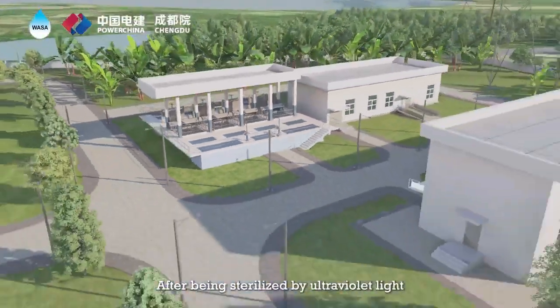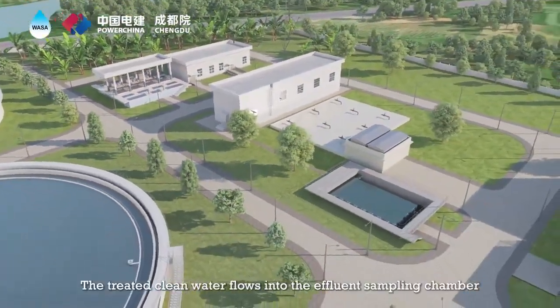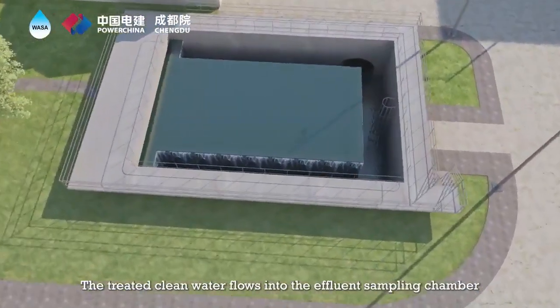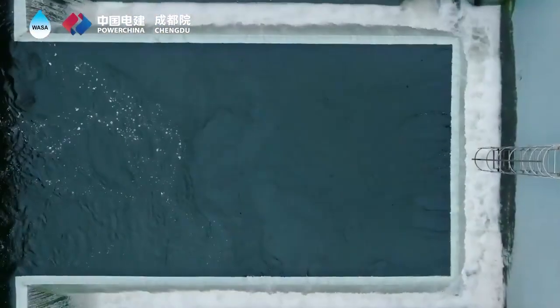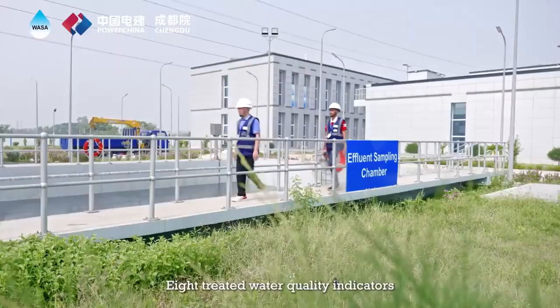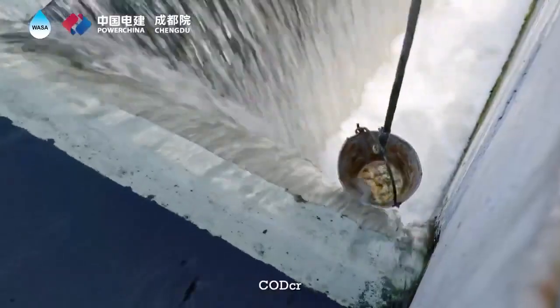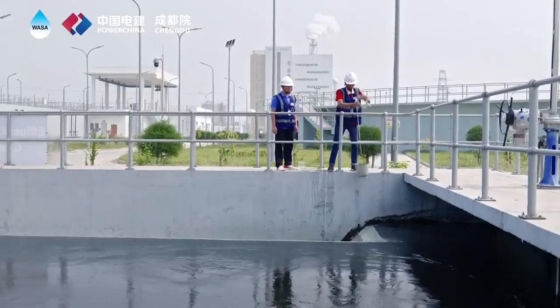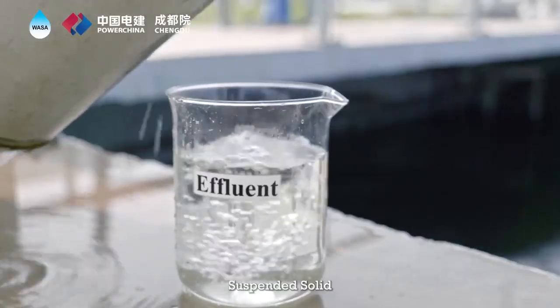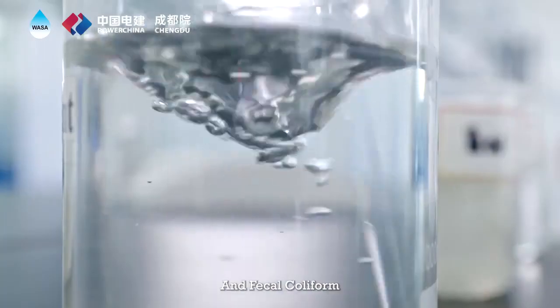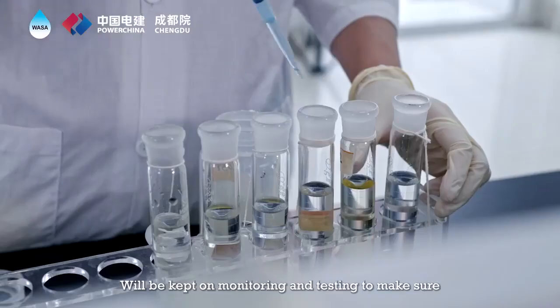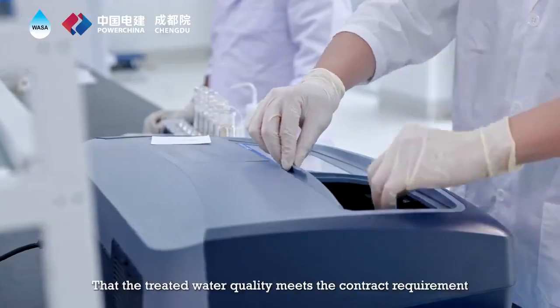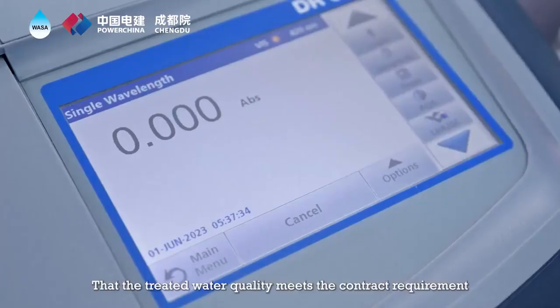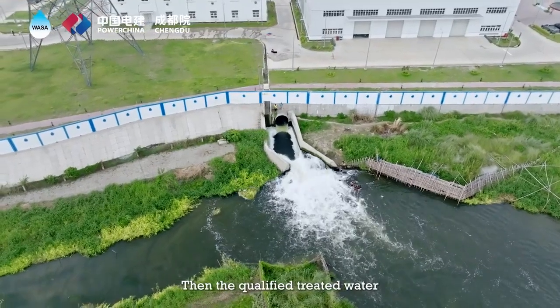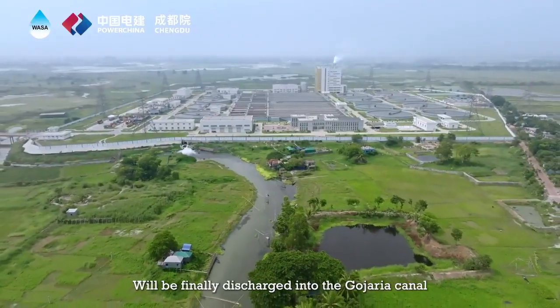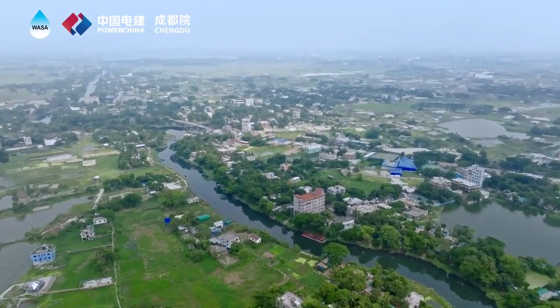After being sterilized by ultraviolet light, the treated clean water flows into the effluent sampling chamber. 8 treated water quality indicators, including pH, COD, BOD, total nitrogen, suspended solid, phosphate, and fecal coliform, will be kept on monitoring and testing to make sure that the treated water quality meets the contract requirement. Then the qualified treated water will be finally discharged into the Gojaria Canal.